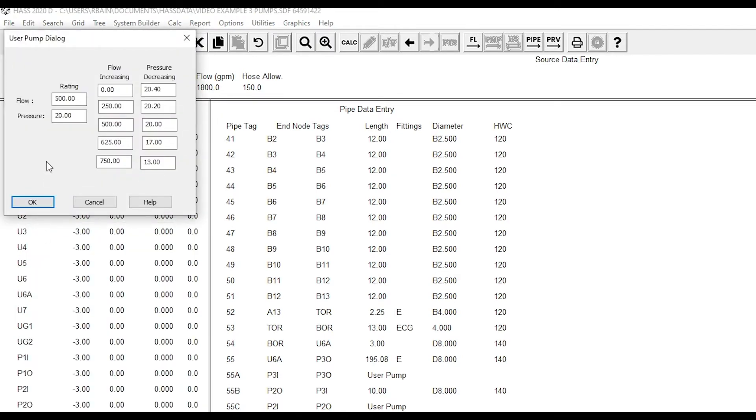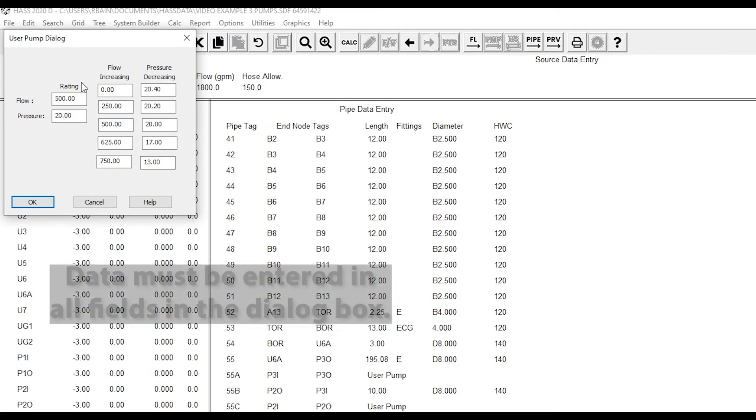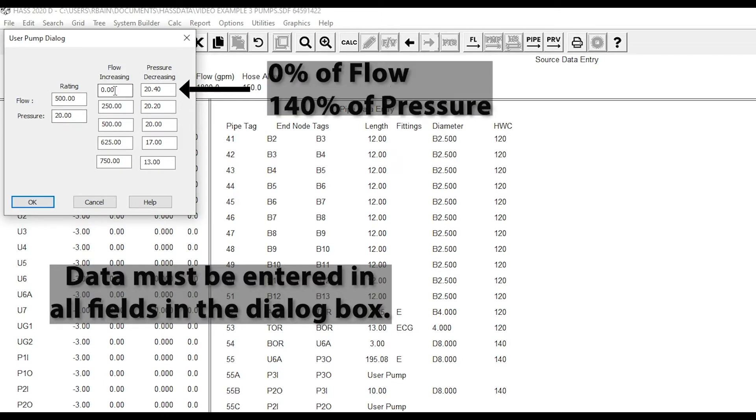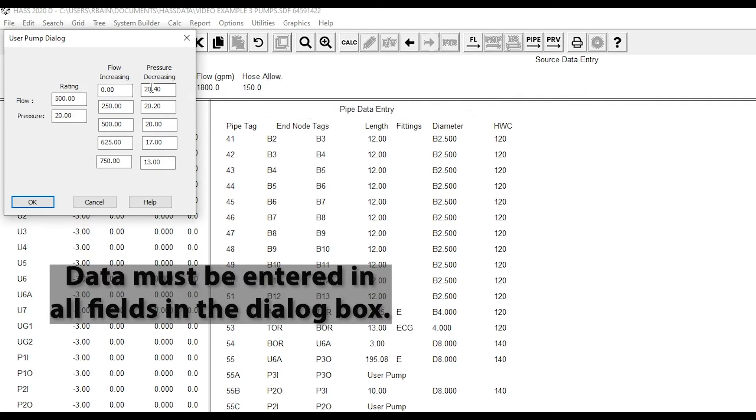This will pop up the user pump dialog. As you can see here, you enter the rating of your pump, flow and pressure, then enter your churn or flow at zero along with your churn pressure, and then your data points.